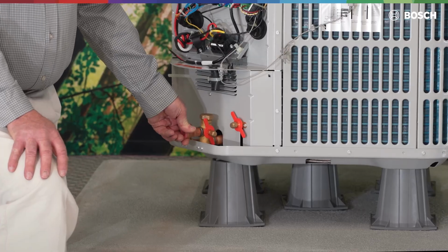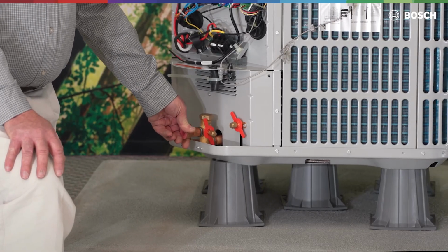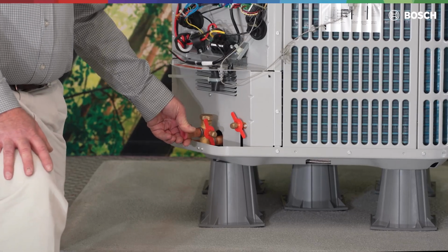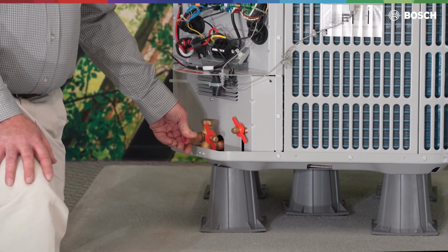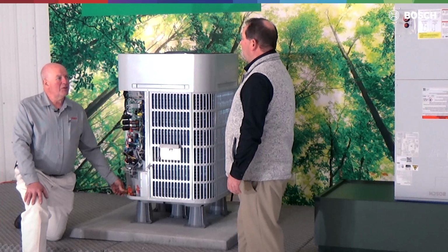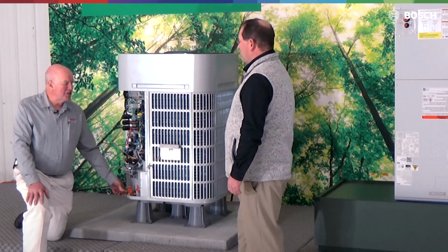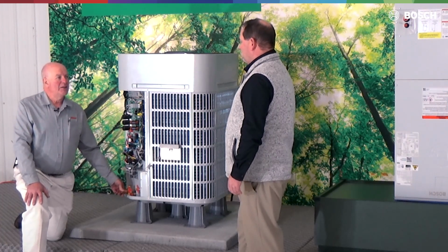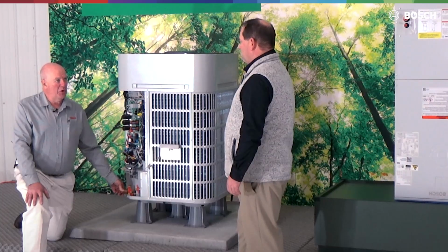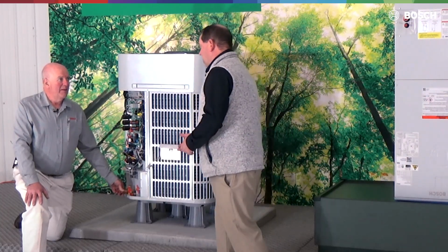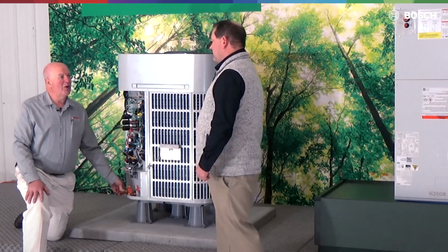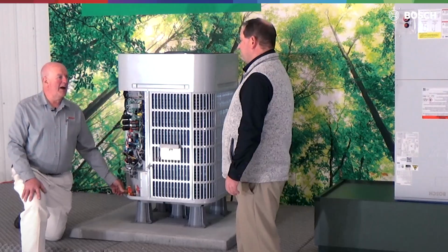Some locations have issues with this. I know one application up in Massachusetts, they have to have a fire watch. When you're in a building with a fire watch, you have to have someone actually stare at that joint for 1 hour to make sure nothing catches on fire when you leave. Okay, but that's if you're going the brazing route. That's correct. So if you go mechanical fittings, you eliminate that issue with the fire watch, which is a big benefit.